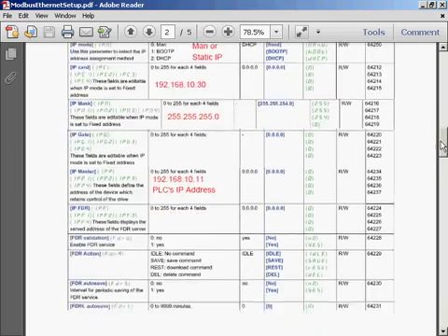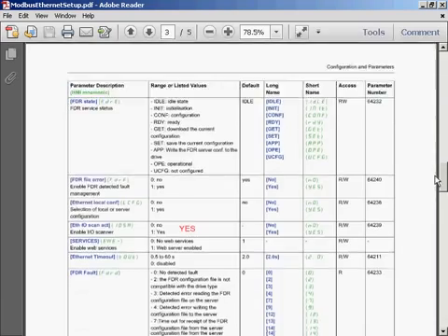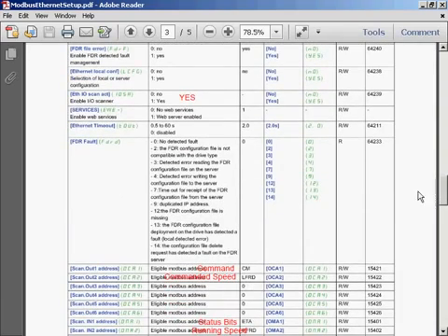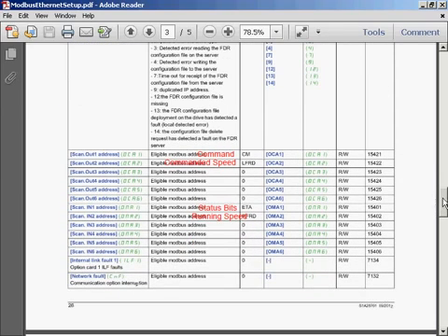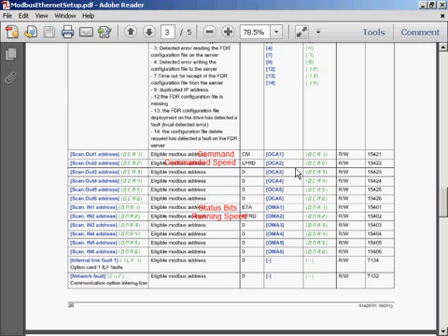As I scroll down further, we'll look at enabling the I.O. scanner. We're going to go ahead and select Yes there. And the default settings for the registers that we're going to control and monitor to command the drive to run and to monitor its current state. This is the default where the first output from the PLC is the control word and the second output is the commanded speed. And then we've got the two inputs monitoring the status and the current running speed of the drive.